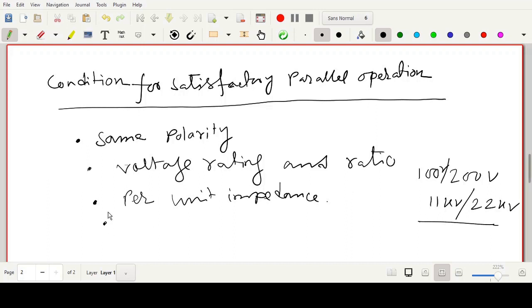Number 4, X by R ratio, reactance to resistance ratio, must be same. Otherwise, this transformer will operate in different power factor angle. So this is another condition required to operate transformers in parallel satisfactorily.